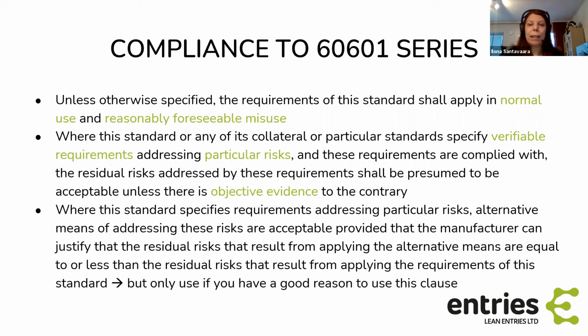And alternative means of addressing some risks are acceptable. The standard does state that, but you should only use this if you have a very good reason to use this clause. So if you have a very complicated device, in the way that you see, for example, a temperature hazard, and it just doesn't make sense that your device shouldn't go over certain temperature limits, or that mechanical hazard tests aren't applicable. So this is an option, but usually it's easier to go with the standard requirements and the test, unless there's a very good reason not to.